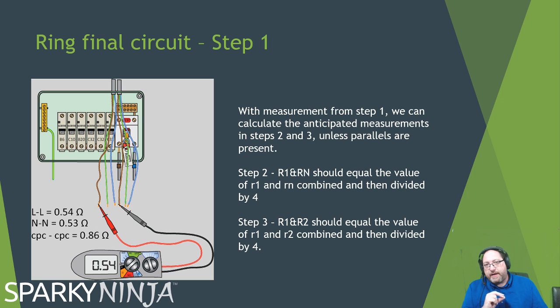We can also calculate step 2 and 3 though once we've done this. So in this illustration here we've got a little r1 or a line to line of 0.54, little rn or a neutral to neutral of 0.53, and a little r2 or a CPC to CPC of 0.86. That's fine, great. Step 2, the R1 plus Rn, we can calculate that because it should equal the line to line value and the neutral to neutral value together divided by 4.